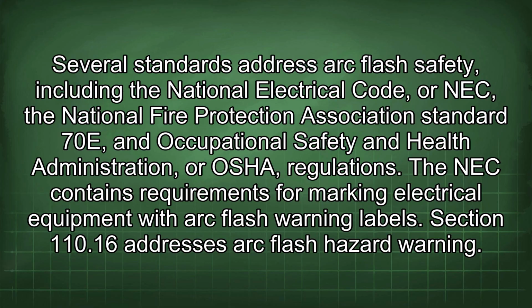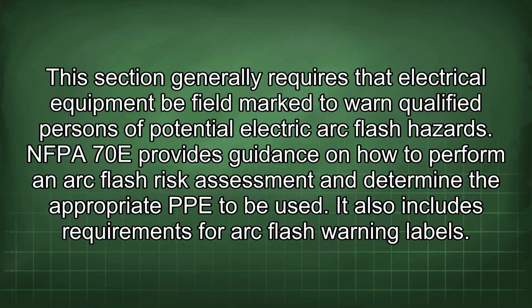The NEC contains requirements for marking electrical equipment with arc flash warning labels. Section 110.16 addresses arc flash hazard warning. This section generally requires that electrical equipment be field marked to warn qualified persons of potential electric arc flash hazards. NFPA 70E provides guidance on how to perform an arc flash risk assessment and determine the appropriate PPE to be used. It also includes requirements for arc flash warning labels.